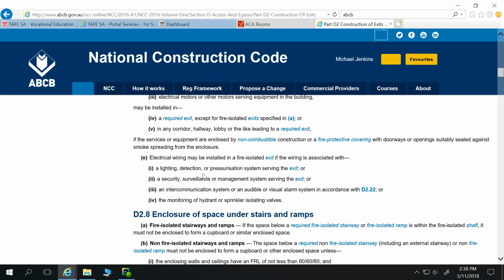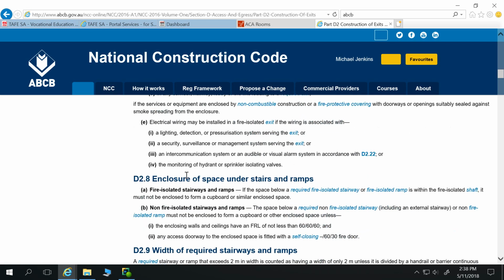So, move on from that. Electrical wiring, of course, there's some exceptions to that though. Electrical wiring may be installed in a fire isolated exit if the wiring is associated with a lighting, detection or pressurization system serving the exit. So some things we need to have in these exits in certain circumstances. A security, surveillance or management system serving the exit, or an intercommunication system or audible or visual alarm system, etc., or the monitoring of hydrant or sprinkler isolating valves. So some of your emergency systems will require power. So our emergency lighting and things like that, they will require power. So we can have those in those emergency exits. But they're the only exceptions.